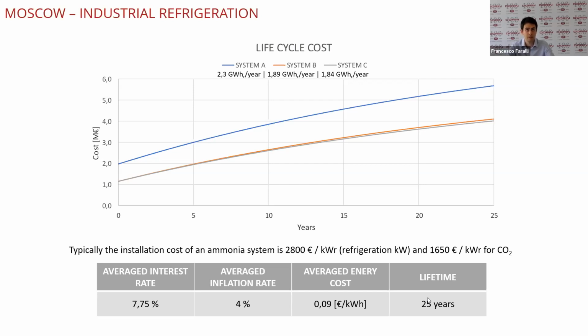And in some countries, here the example was made in Moscow, thanks also to the very good COP of the CO2 system, we have the life cycle cost of the system that is much lower for CO2. In fact, CO2 is starting from a lower point in year 0 at the installation, but also the gap between the CO2 and ammonia increases during the years because of the higher COP of the CO2 system.